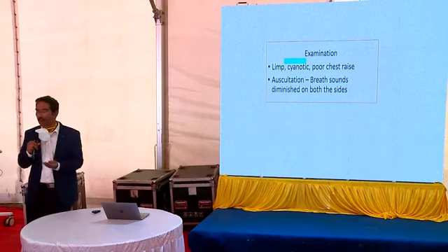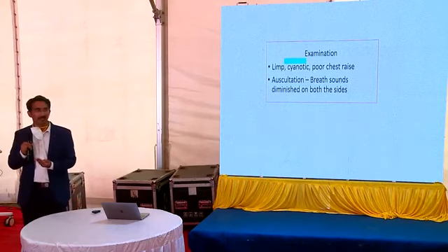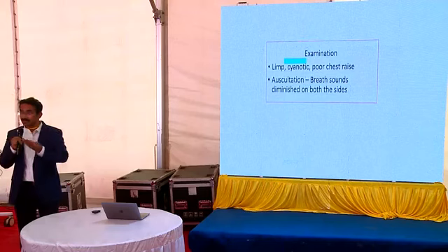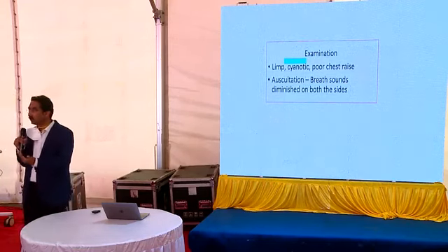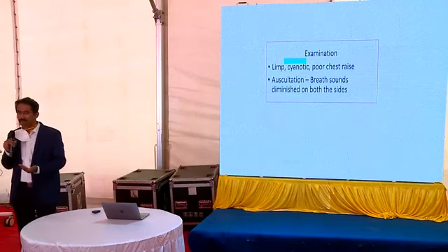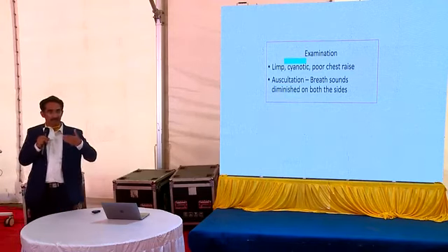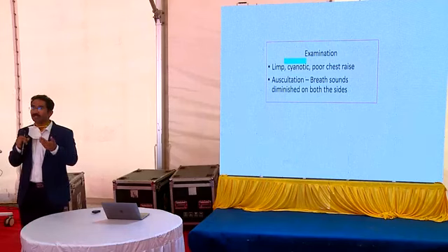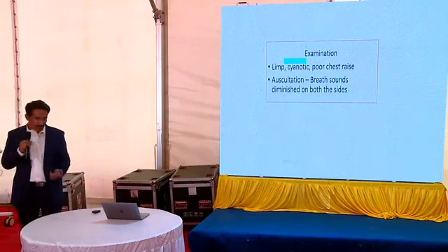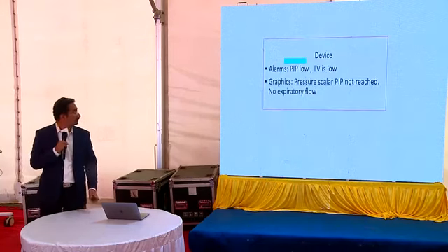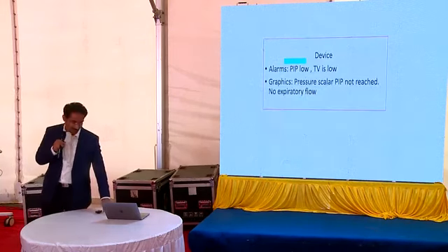Excellent. Endotracheal tube can be blocked, or there is inadequate ventilation. That means the ventilator is not delivering the set pressures, hence the set volumes are not being generated. It can be because you have inadvertently or inappropriately set the parameters on the ventilator wrong, or there is an equipment failure. So what we should do is examine the ventilator graphics.